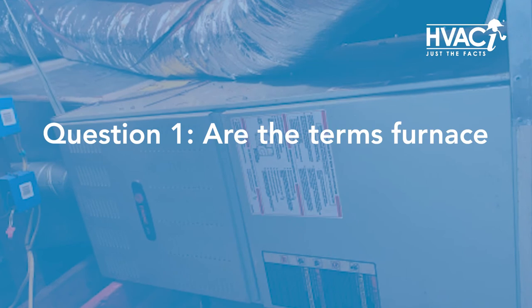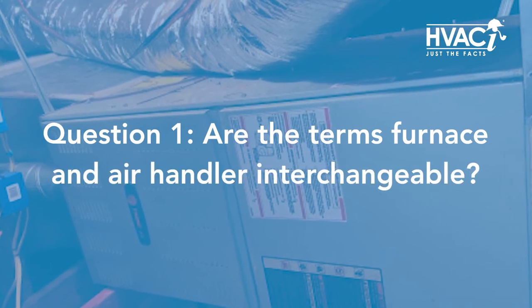First question today is, are the terms furnace and air handler interchangeable? The answer is no. An air handler and a furnace are two different things. An air handler is for air conditioning only, with the two main components being the evaporator coil and the blower. A furnace, which might also be an air handler using that evaporator and blower, has heating components added, like a gas line or oil line coming in. It also has the burners and heat exchangers to generate that heat. So they are two very different pieces of equipment.